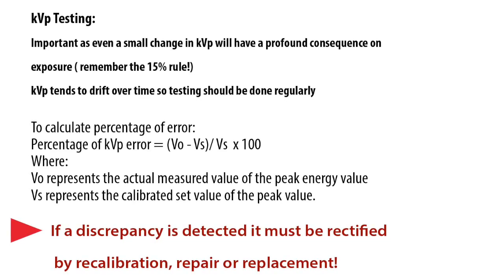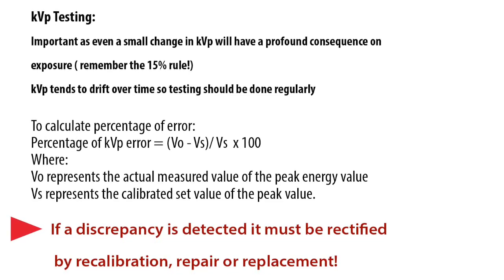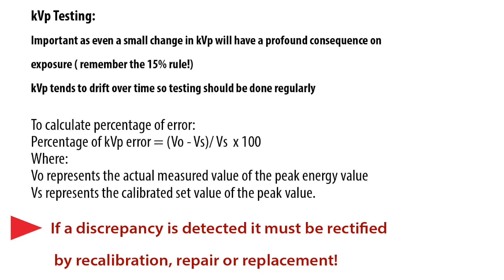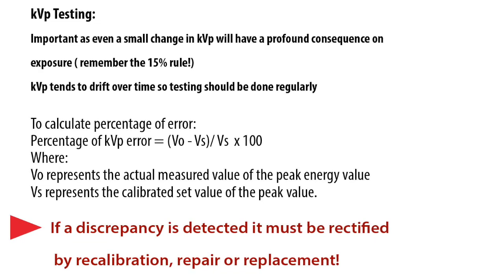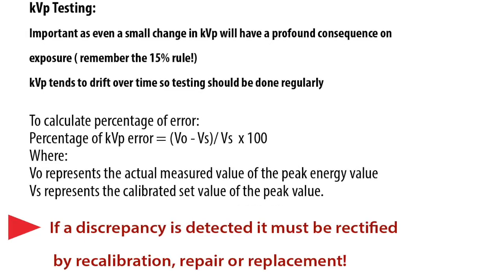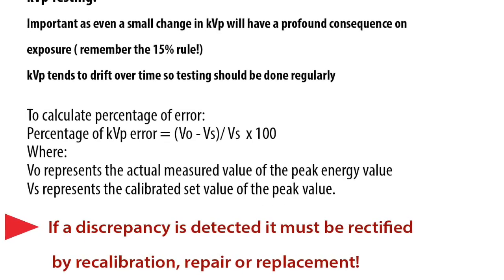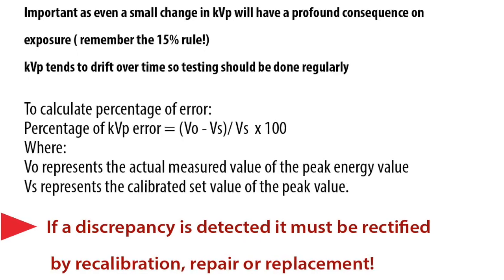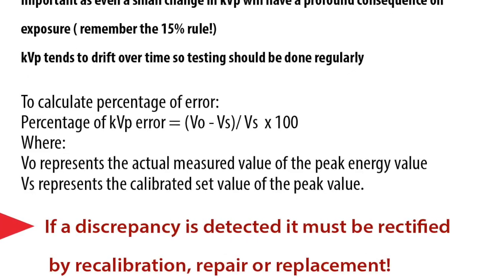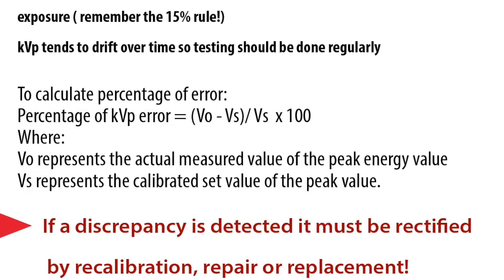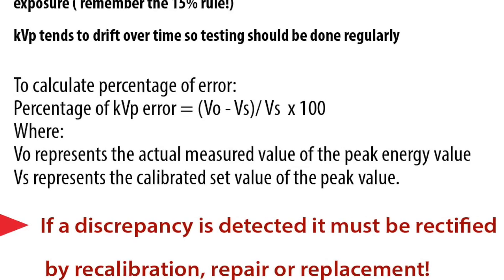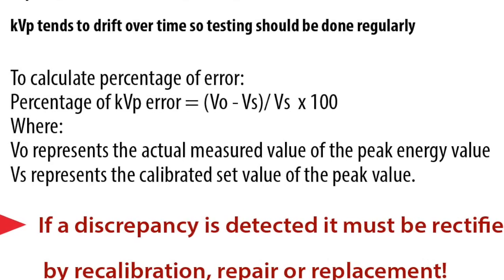KVP accuracy is tested using a digital KV test meter or a computerized dosimeter. When various KVs are tested within the diagnostic range, the selected KVP and actual peak energy of the output beam should not differ by any more or less than 4% KV of the calibrated setting for general diagnostic equipment and not more or less than 5% KV of the calibrated setting for mammography equipment.